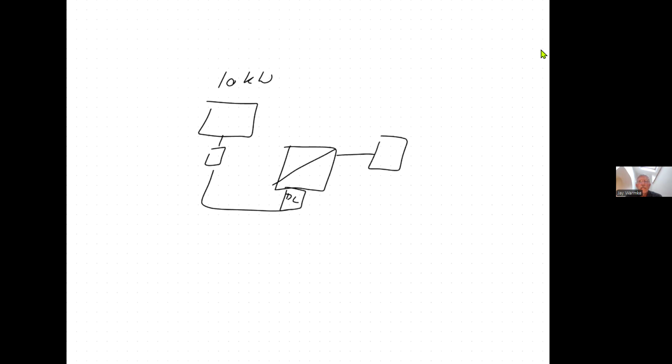So in this case, I've got my array, it's going to a junction box. From the junction box, it's coming up here to a DC disconnect, and then that DC disconnect is connected to my inverter. And this is a string inverter system. From the string inverter, we're going to go to typically an AC disconnect. That's got to be located, chapter 5, within 10 feet of the meter, externally operable, lockable, clearly marked, right? The utility wants to see that AC disconnect out there next to the meter.